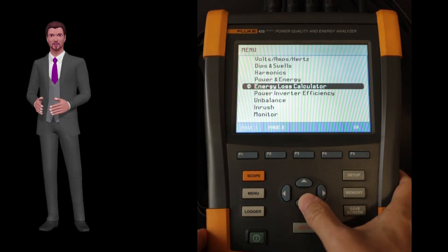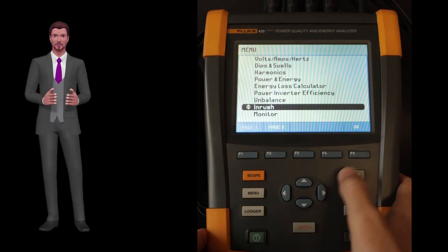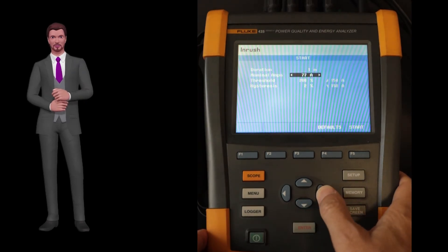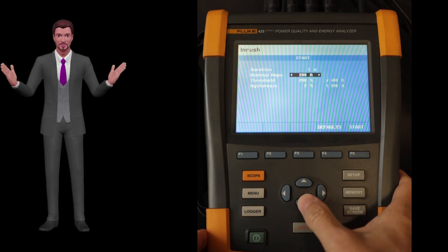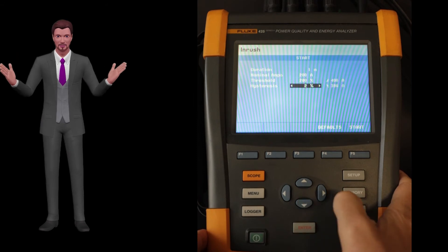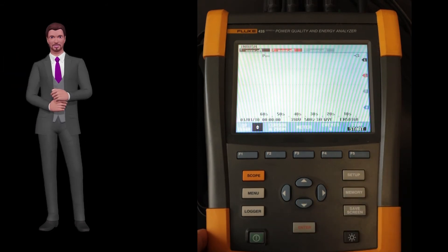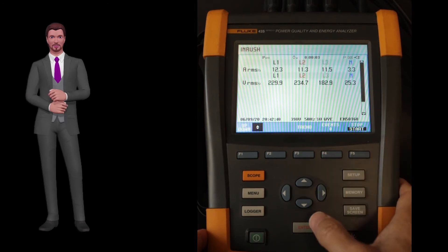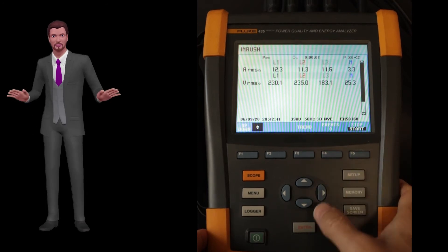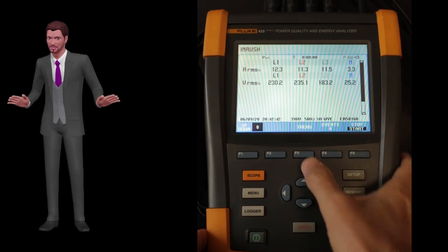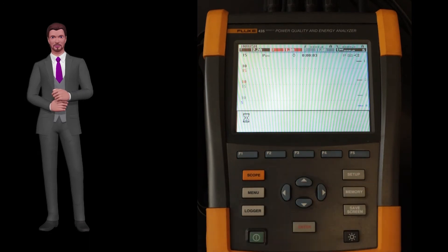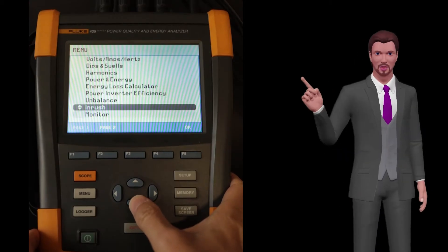The inrush function is used to measure the starting current of motors. This current must be measured following a special procedure so that it really reflects the current that would be perceived by the electrical protection that should protect the motor without unnecessary tripping. In this case we have to define the current level that triggers the data capture.